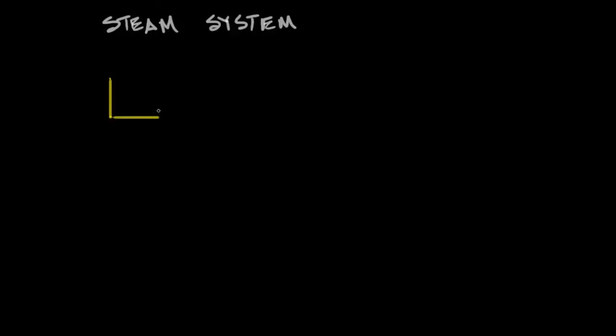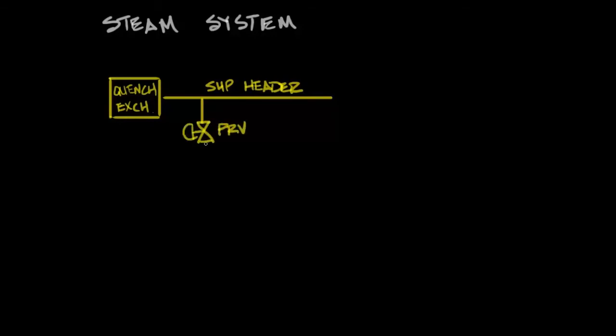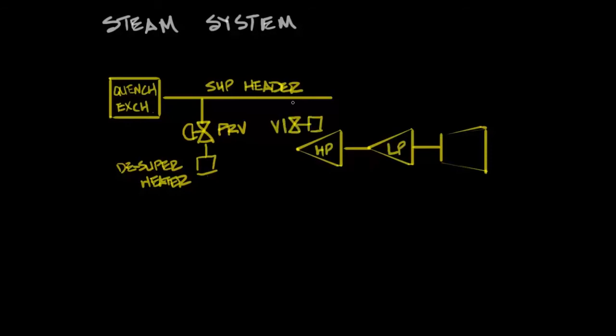Let's take a look at what our steam system looks like. We'll draw the quench exchanger just as a simple box. Out of that box comes the super high pressure steam. On that header will be some kind of a pressure reducing valve to dump off excess steam if the turbine can't handle it. But most of the steam if not all is going to go through V1 of the crack gas compressor. That'll be a two section extraction turbine with V1 handling the 100 bar steam and then extracting steam to the high pressure header which is usually around 40 bar.